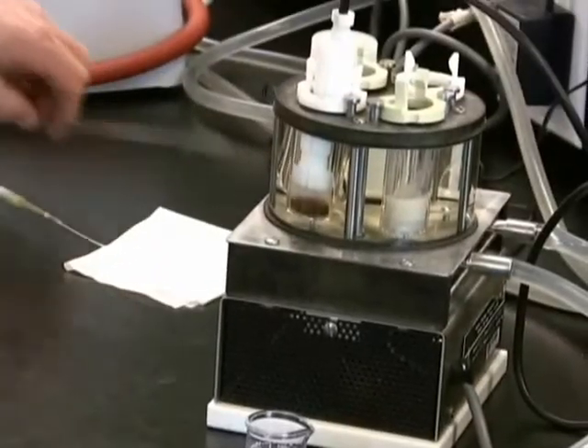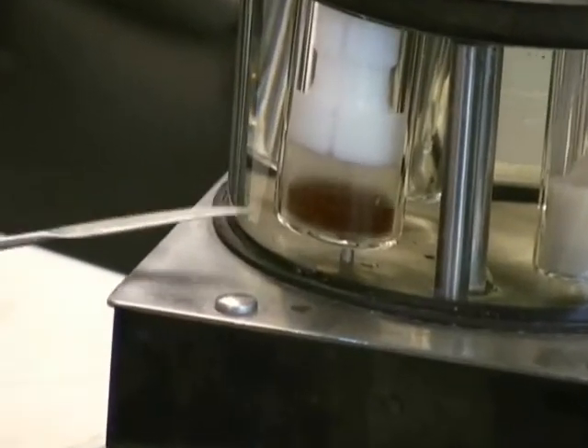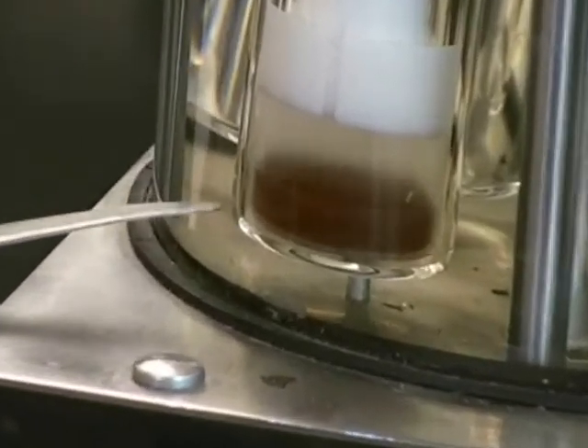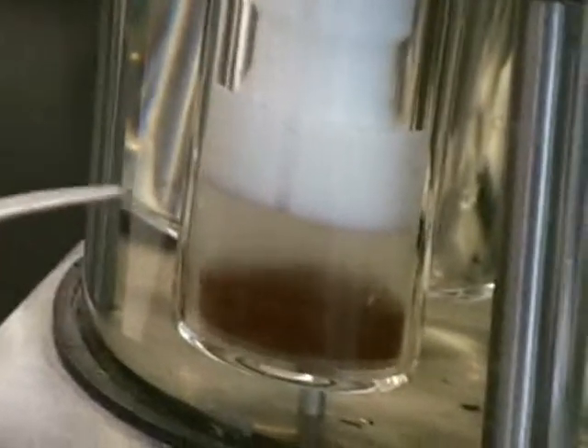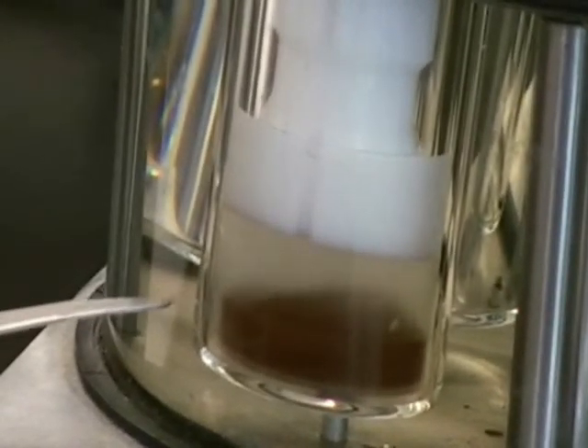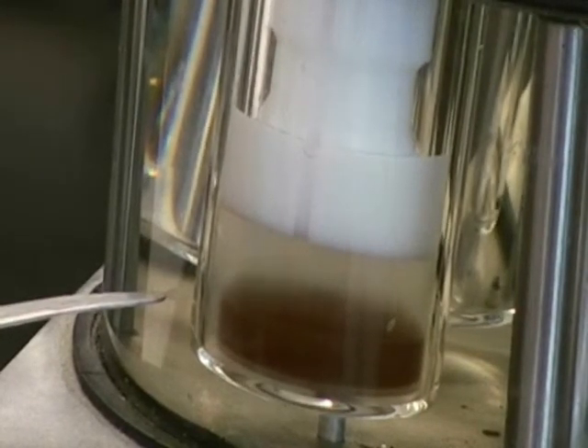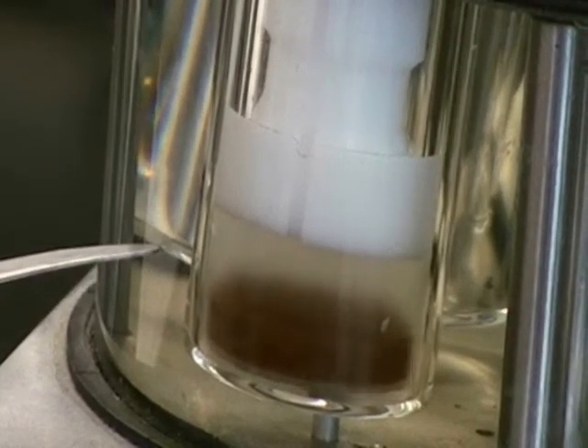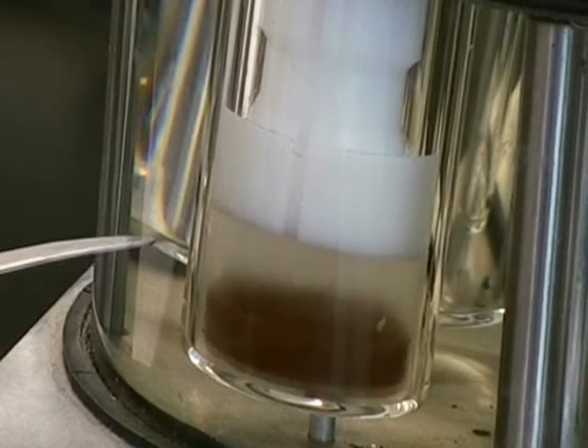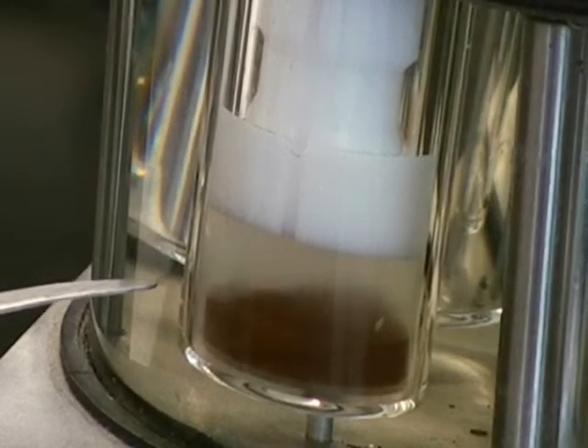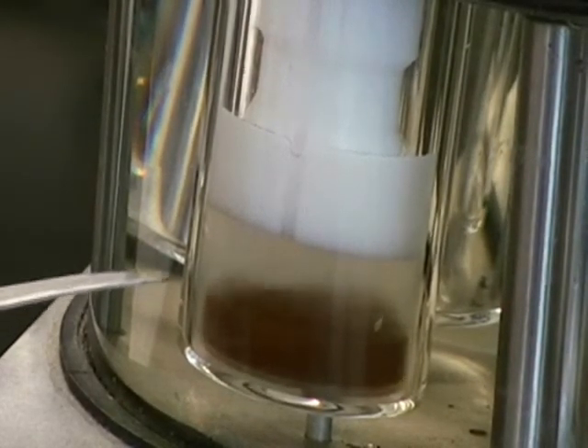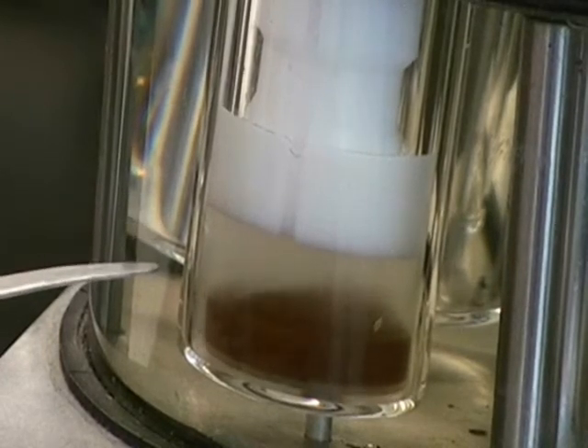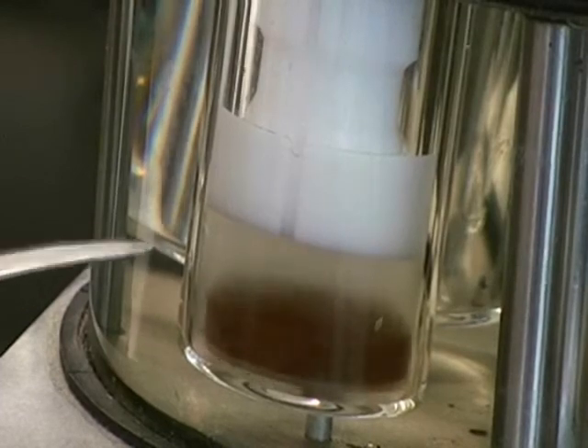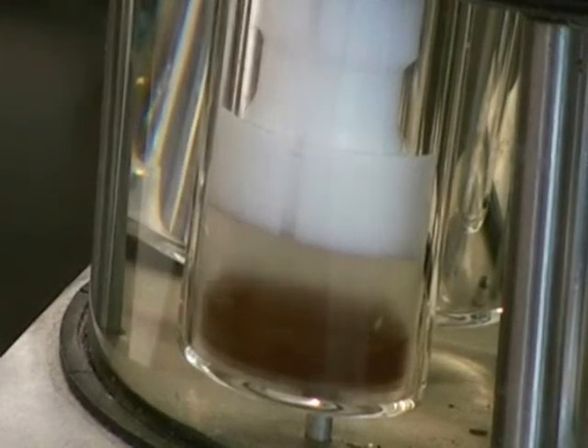Now the yeast has been added to our chamber. It is kept homogeneous by the magnet. Now initially we calibrated the signal coming from the buffer at 100%. Now the yeast is in there consuming the oxygen from the buffer. Therefore we're reducing the amount of oxygen available to equilibrate with the platinum, so we have a decrease in concentration, and this will be amplified by the unit and then recorded.